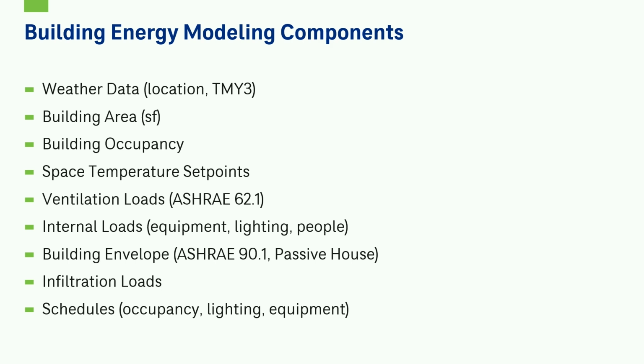The next one is your building area, the square footage. Depending on how big your building is, that's really going to drive the heating and cooling loads. Also, the building occupancy is going to drive your temperature set points. If it's an occupied residential space, it'll be anywhere from 70 to 75 degrees. Typically, if it's an unoccupied mechanical space, your heating set point might be more around 50 to 55 degrees. And then the building occupancy also determines when the heating and cooling is required. When do you have people in the building? Is it a residential building where people are typically home in the morning and the evenings? Now with work from home, are they there all day? And in an office building, are they typically there on more of a 9 to 5 basis? And when are those loads happening that you're going to need the heating and cooling?